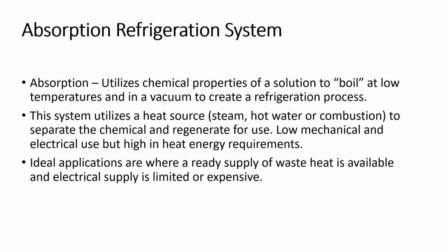These were very popular back in the day where you did not have as great an electrical infrastructure or as much power generation as we have today. Plus, if you had a factory or somewhere that you had a lot of waste heat, these would really be good because they use heat to operate. They have to have a heat source in order to drive off and separate those chemicals and recycle them. So if you had a manufacturing process or a plant that used a lot of steam or combustion, or you were out in the middle of nowhere where you didn't have a lot of electrical power, or you only had a generator that only had a certain capacity, and you needed chilled water, then this was an option, because you had a ready source of free or sideline process heat available, like on a ship. They used a lot of absorption on naval ships because they generated steam for propulsion, and so they used the steam also to generate cooling.